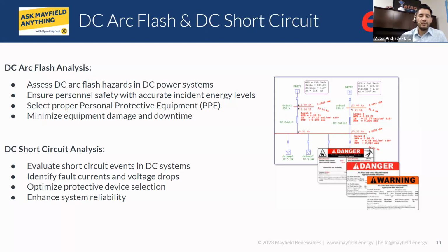The PPE is by categories like level 1 or category A, B, C, depending on the amount of heat the explosion releases. So you probably know of a 4-calorie, 8-calorie PPE suit. Most all of us, when we're in the field, are going to be wearing at least an 8-calorie, right? Which is the long sleeve overall, the shirt, the pants. However, there are locations where the incident energy may be above 12, 24, 25 calories per centimeter square, and there's a different PPE that must be worn. So these labels let the electrician or the person working on the live equipment know before they open the panel what type of PPE to wear.